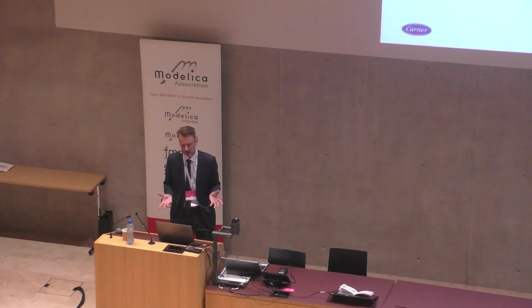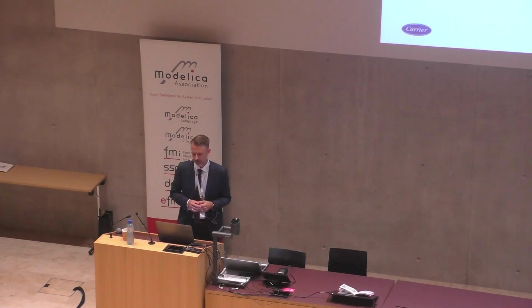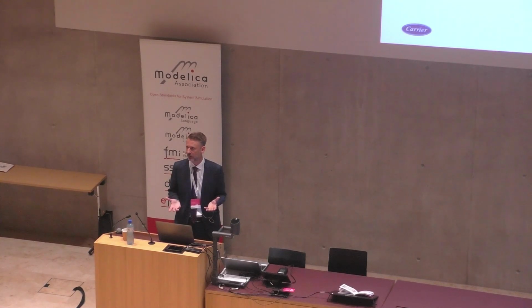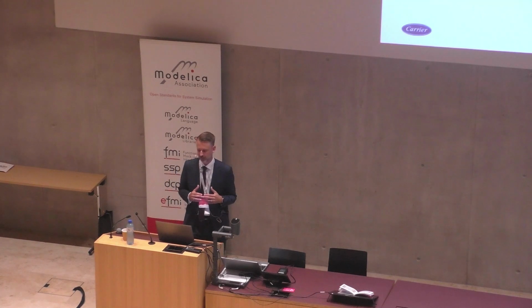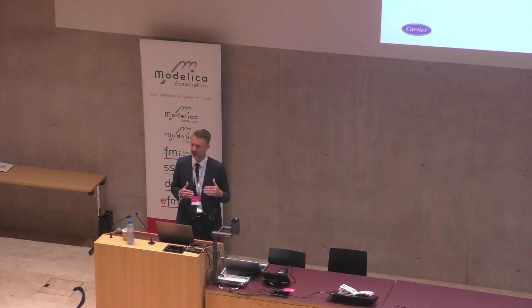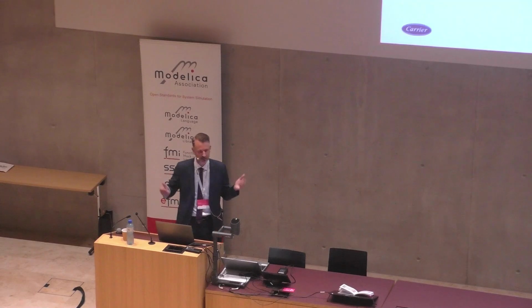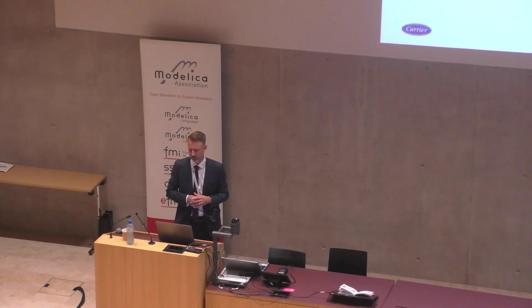And we can save quite a bit, at least for this case. So we compared the baseline installed control system. Maybe we start to the right. The blue curve is the baseline controls. The baseline control system runs fairly few chillers for a given load, and it doesn't stage up and stage down very much. It runs roughly three chillers. That's a good number for these load conditions. And the optimal solution shows that for these particular chillers, it's much more advantageous to run more chillers, because these chillers have a free cooling option.